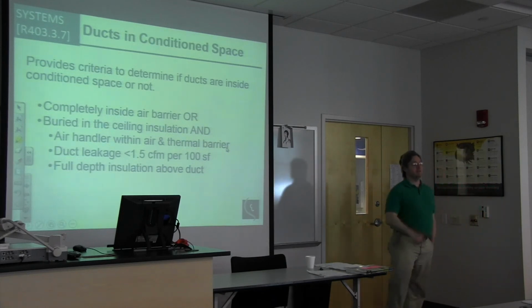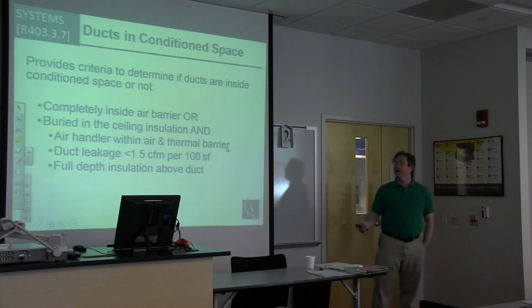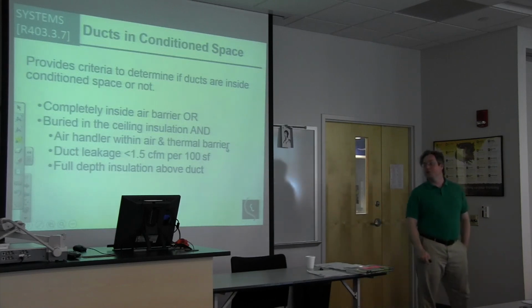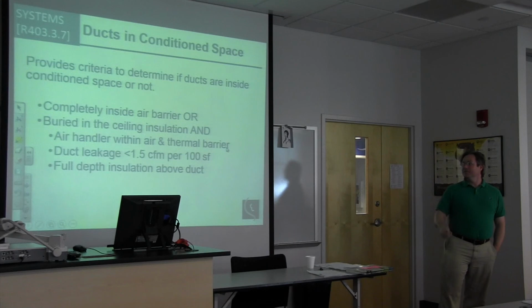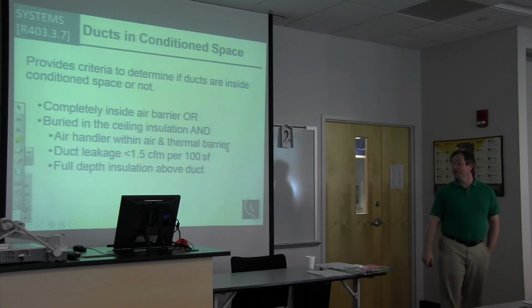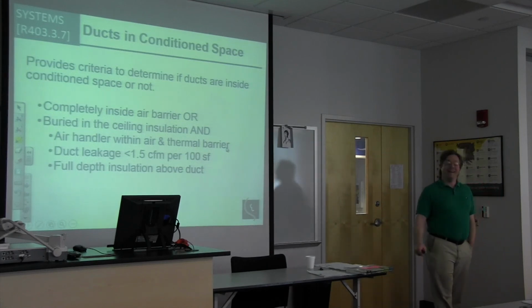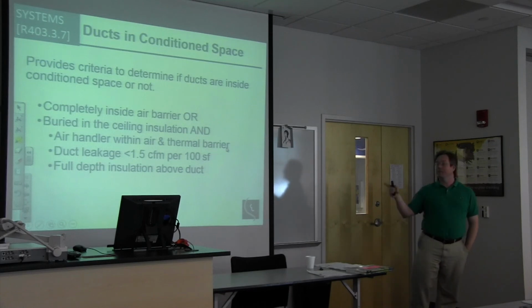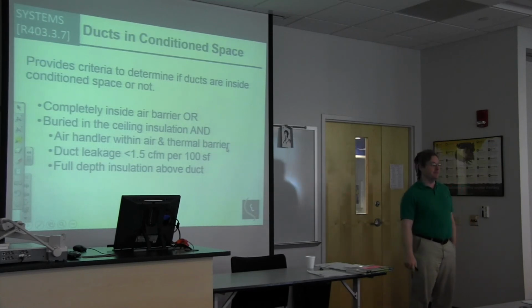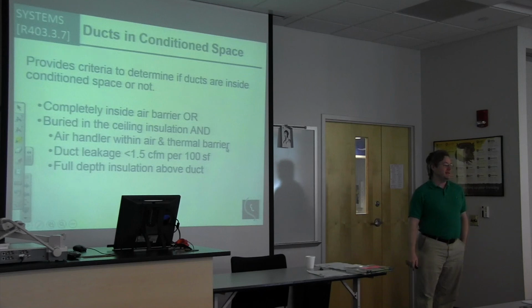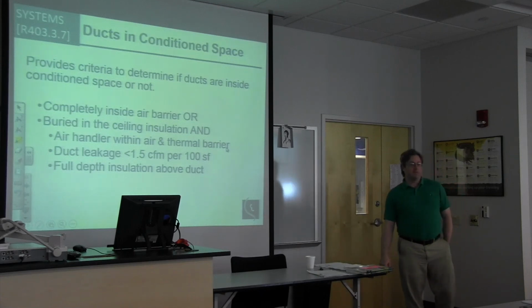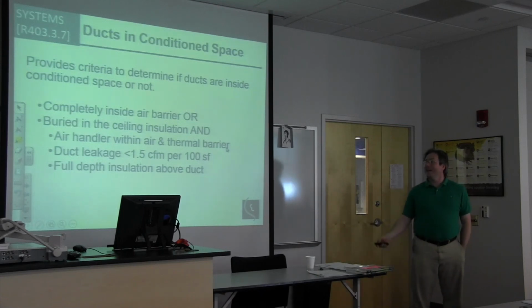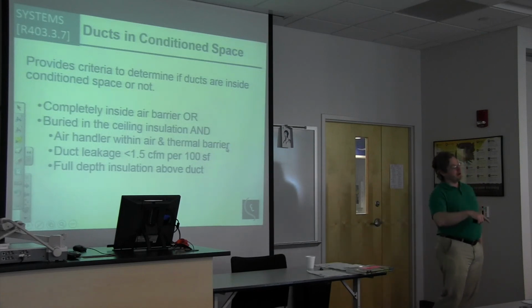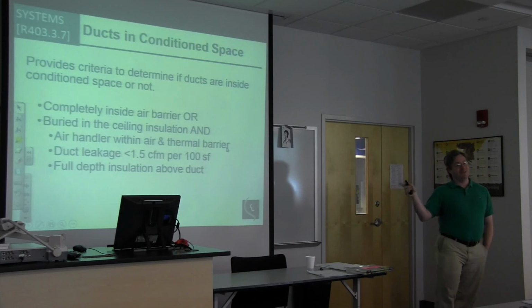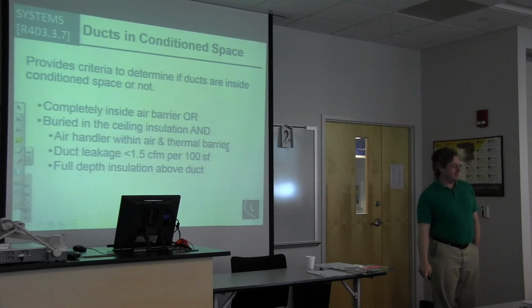So this gets back to your duct testing. Yeah. If you're buried in the ceiling insulation and your air handler is within the air and thermal barrier, your duct leakage testing has to be less than 1.5 CFM per 100 square feet. So they're still going to have to test it either way if they choose that path. So you're going to have to test, and full depth insulation above the duct. So the R49 above the duct and extremely tight ducts.